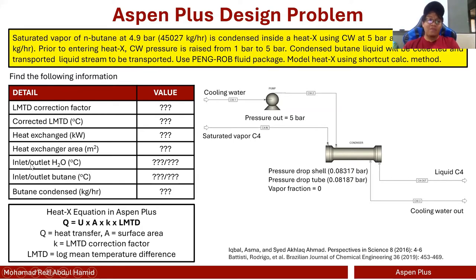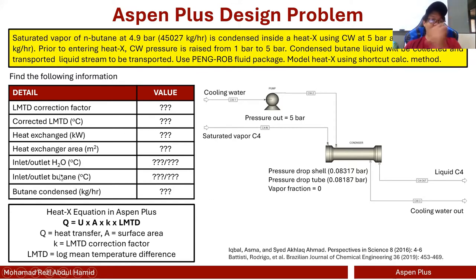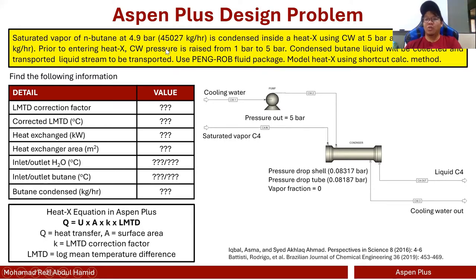These are all the necessary outputs we need to extract from our heat exchanger simulation: the LMTD correction factor, the corrected LMTD (log mean temperature difference), how much heat is being transferred, the heat exchanger area, inlet and outlet cooling water temperatures, inlet and outlet butane temperatures, and the amount of butane condensed. Since we are attempting to condense all of the n-butane, the amount to be condensed is 45,027 kg/hr.